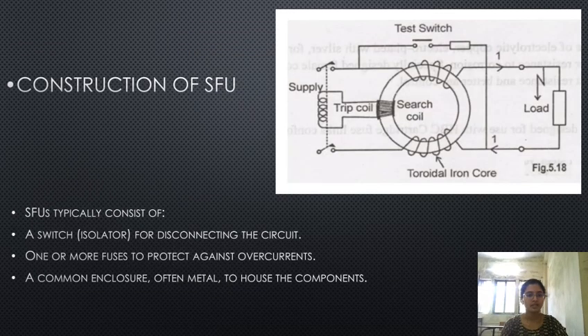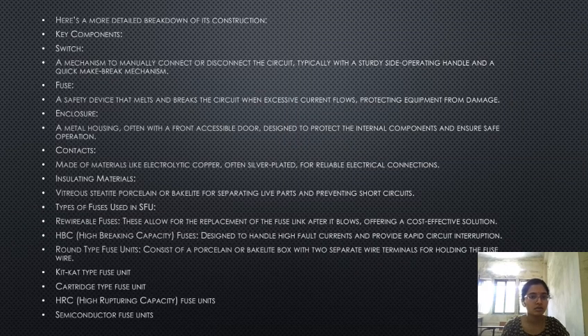Construction of SFU. SFU typically consists of a switch for disconnecting the circuit, one or more fuses to protect against overcurrents, and a common enclosure, often metal, to house the components. Here is a more detailed breakdown of its construction. Key components: a mechanism to manually connect or disconnect the circuit, typically with a side operating handle and a quick make-break mechanism with a switch. A metal housing, often with a front accessible door, designed to protect the internal components and ensure safe operation, is called an enclosure.